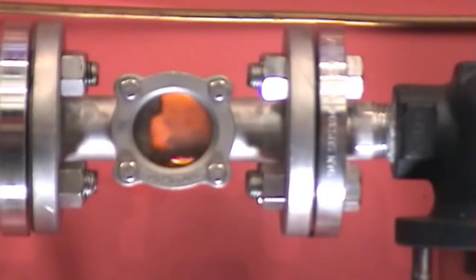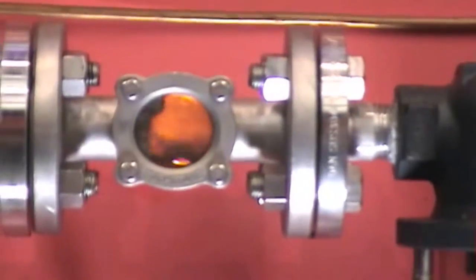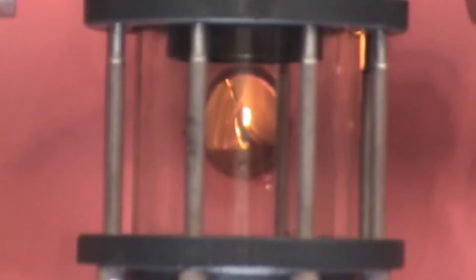This wet steam contains condensate as either a stream or tiny entrained droplets that reduce thermal efficiency and can cause water hammer or corrode and erode equipment. It can also reduce heat transfer rates in heat exchange components.